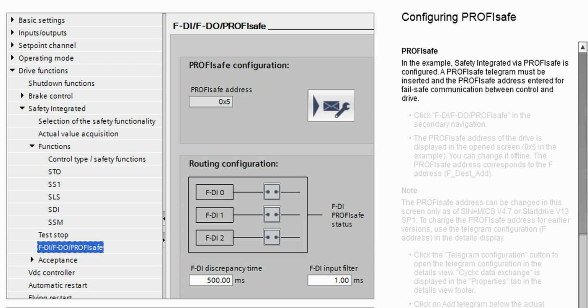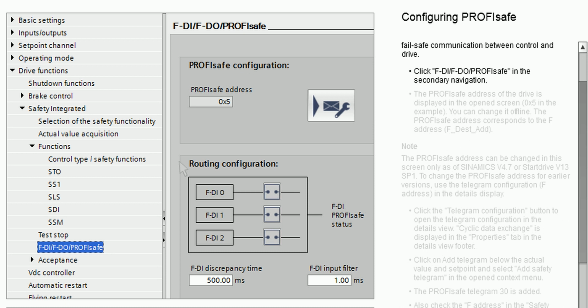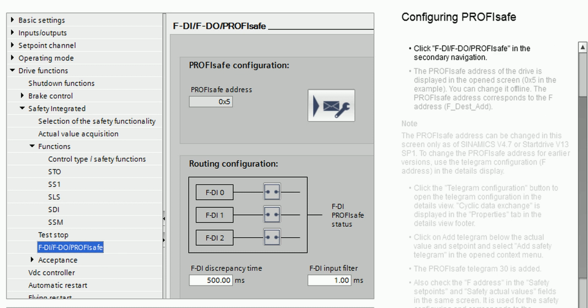PROFIsafe. In the example, safety integrated via PROFIsafe is configured. A PROFIsafe telegram must be inserted and the PROFIsafe address entered for fail-safe communication between control and drive. Click FDI, FDO, PROFIsafe. In the secondary navigation, the PROFIsafe address of the drive is displayed in the open screen, 5 in the example. You can change it offline. The PROFIsafe address corresponds to the F address, F_Dest_Add.